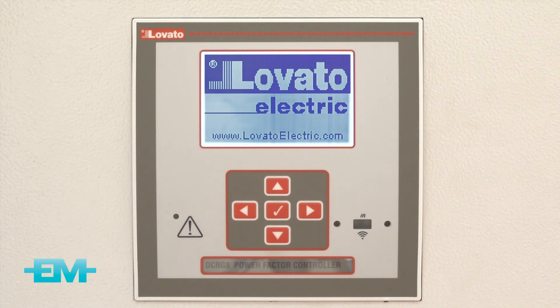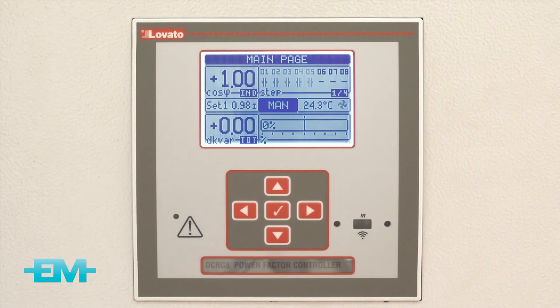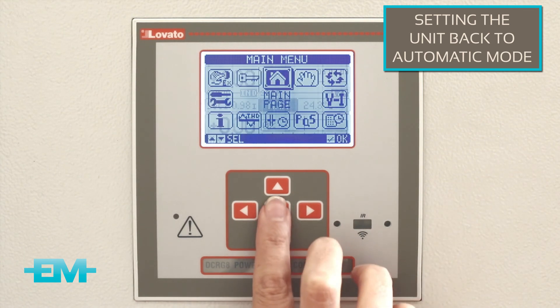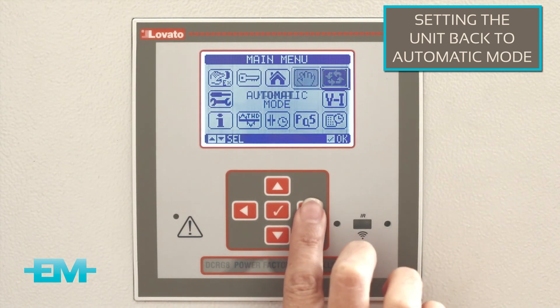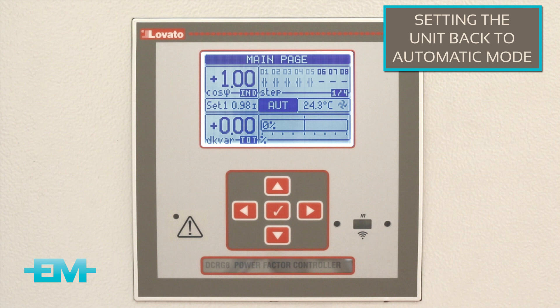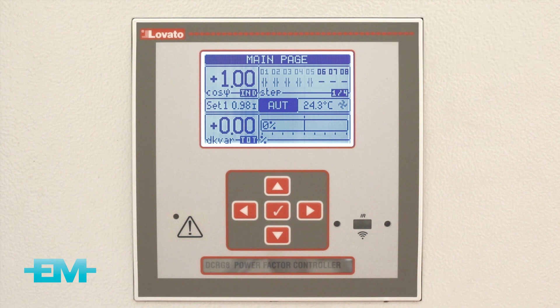Once you have completed all settings and the controller has reset, ensure that you set the unit back to automatic mode. This is done by pressing OK to return to the main menu, scrolling right to the automatic icon, and pressing OK once. The unit will return to the main page and will display the auto mode. It will take approximately 60 seconds before the capacitor steps start being selected. The setup is now complete.